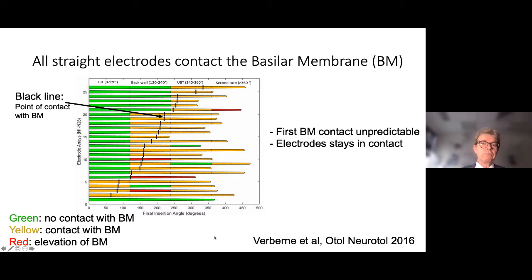Here is some work from Verberne that we published in 2016, using the temporal bones for the FDA approvals of the slim straight electrode. Green indicates no contact with the basilar membrane, yellow indicates some contact, and red means the basilar membrane is being pushed up. With most electrodes there is no actual upward pressure on the basilar membrane, but there is proximity. The point where contact first occurs varies considerably across the cochlea, but once it occurs, in almost all cases the contact will remain.